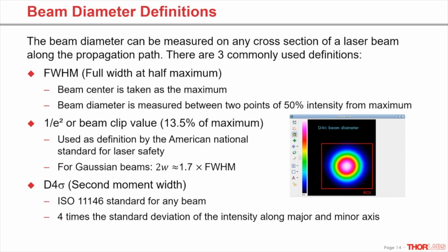By calculating the second moment of the beam profile, it is possible to characterize all kinds of higher mode beams as well. However, it is very important to compensate against background light and not saturate the sensor at the maxima.